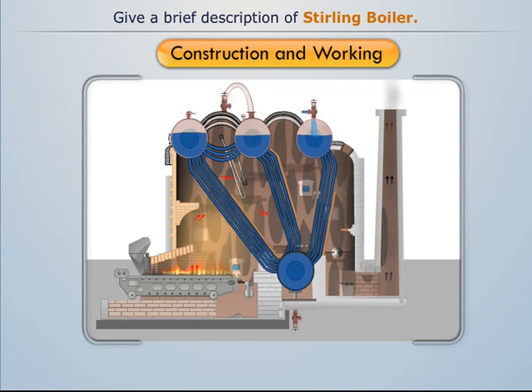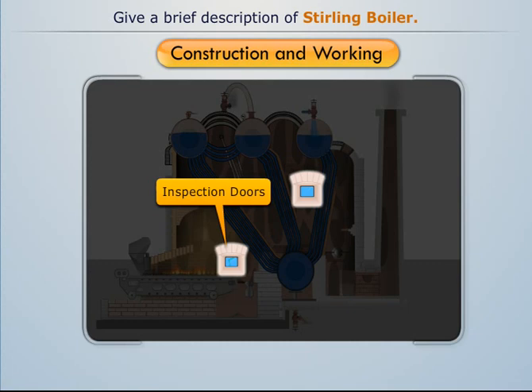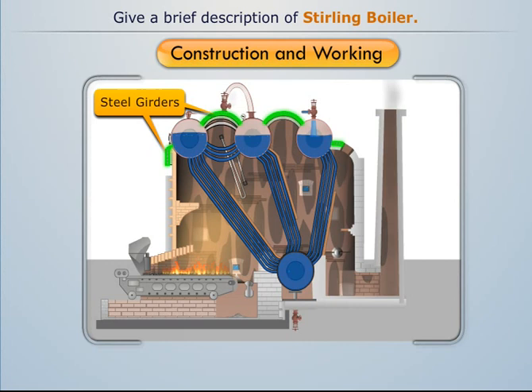Ash produced by the burning of fuel is collected in the ash pit, while smoke is allowed to escape into the atmosphere through a chimney. A damper is installed before the chimney to regulate the air supply into the firebox. Inspection doors are provided in the boiler to inspect its operation on a regular basis. The boiler assembly is suspended on steel girders to enable the boiler drum and water tubes to expand and contract during operation.